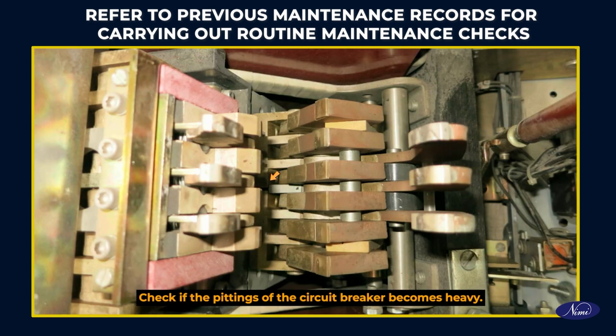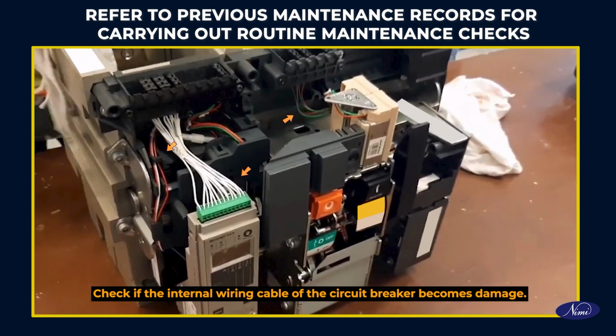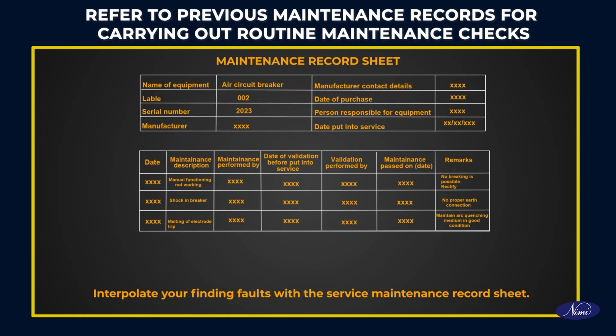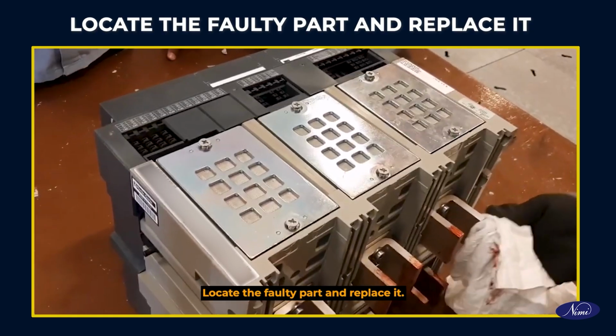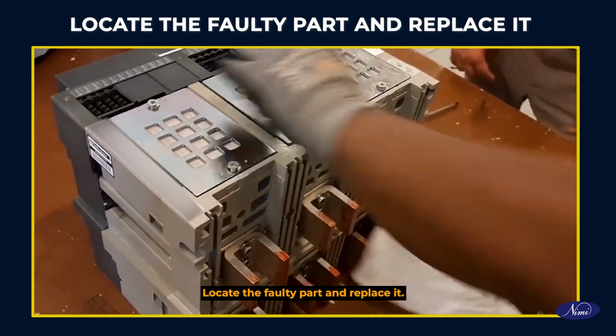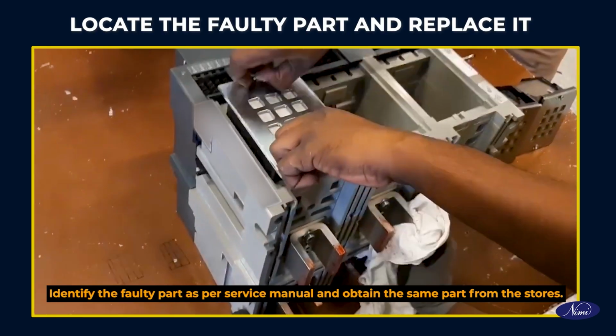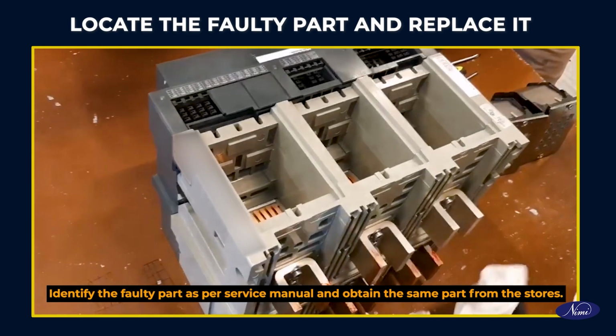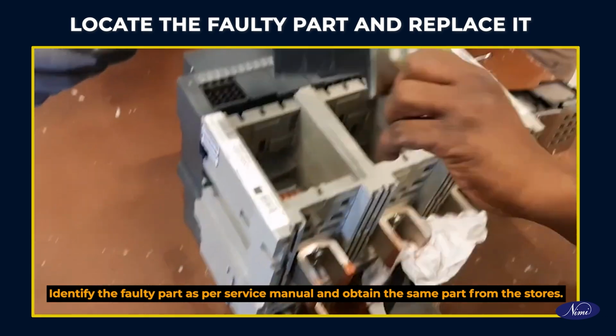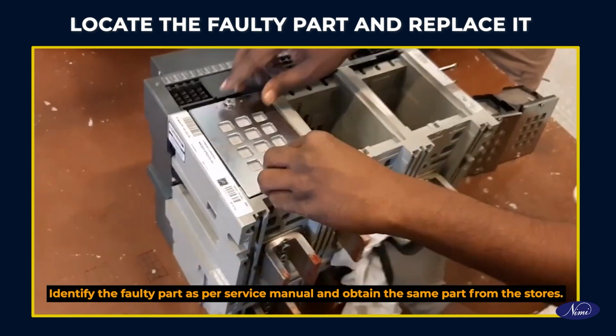Check if the pittings of the circuit breaker have become heavy. Check if the internal wiring cable of the circuit breaker has become damaged. Correlate your findings of faults with the service maintenance record sheet. Locate the faulty part and replace it. Identify the faulty part as per service manual and obtain the same part from the stores.